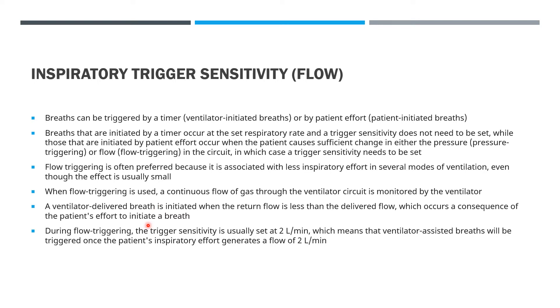During flow triggering, the trigger value is usually set at 2 liters per minute. This means a ventilator-assisted breath will be triggered once a patient's inspiratory effort generates a flow of 2 liters per minute.